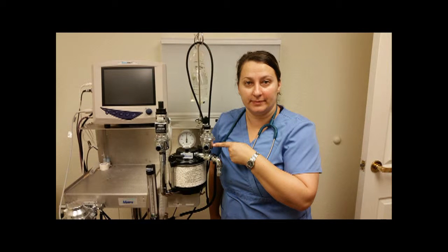Inspiratory unidirectional valve directs oxygen and anesthetic agent toward the patient in inhalation. It opens on inspiration or inhalation and closes during exhalation. It creates unidirectional flow of gases and prevents rebreathing of exhaled gases before their exposure to carbon dioxide absorbent.